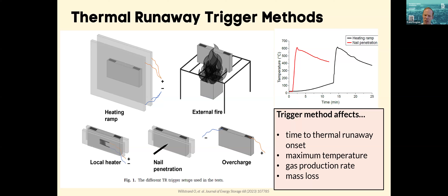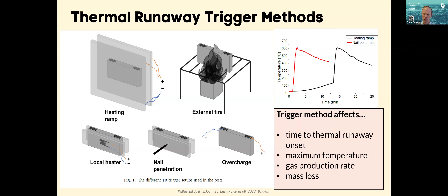The trigger method definitely affects the time to thermal runaway onset, the maximum temperature, the gas production rate, and also the mass loss. In this graph on the right, you can see how we expose the same battery to nail penetration and to a heating ramp, which affects the development of the thermal runaway in a major way—there was a delay of about 12 to 13 minutes until we achieved about the same thermal runaway in this cell. So in addition to the state of charge, which Maria showed before, the trigger method is very important for the gas production rate, the mass loss rate, and the thermal runaway onset temperature.